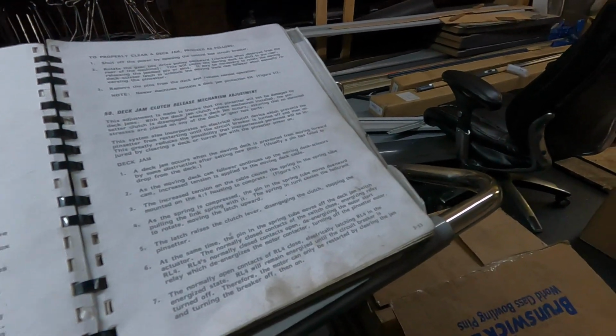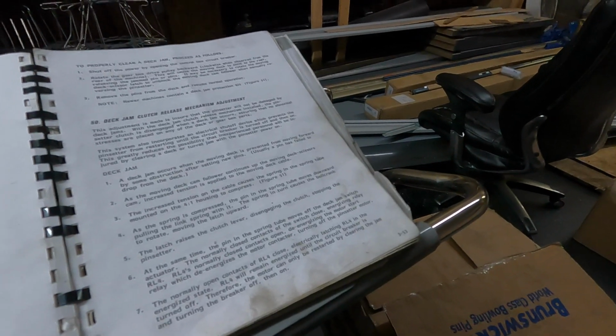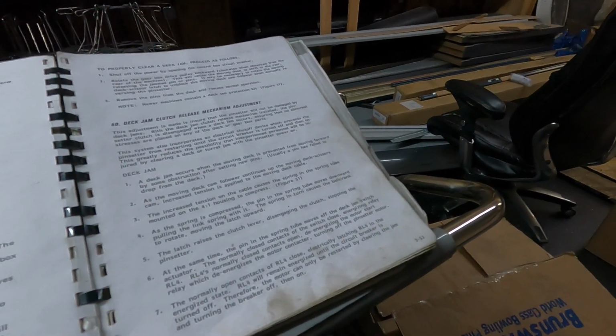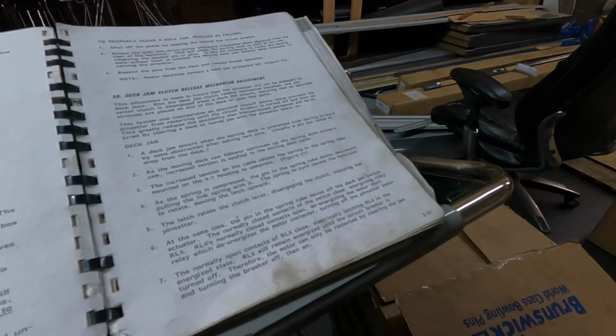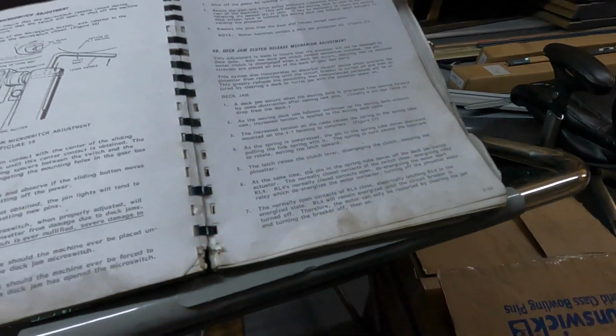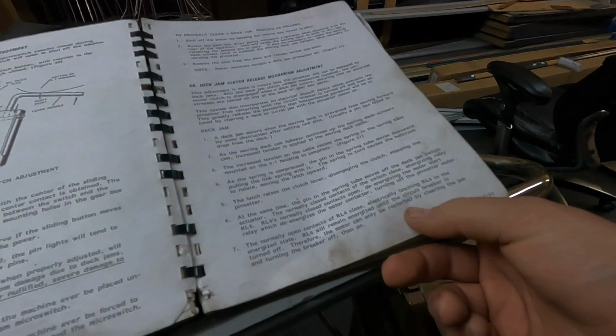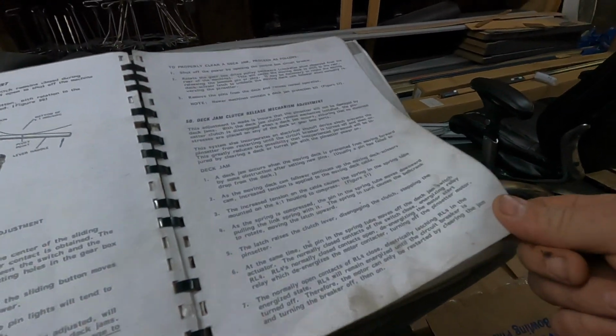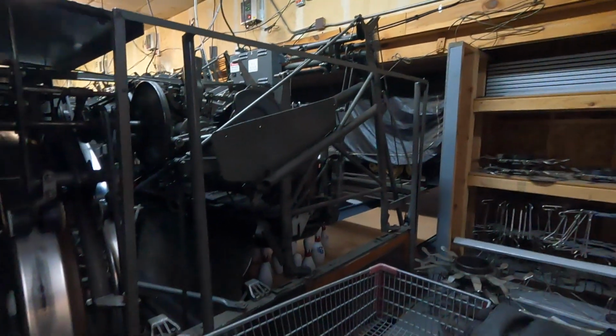Normally open contacts on RL4 close, electrically latching RL4 in the energized state. RL4 will remain energized until the circuit breaker is turned off. Therefore, the motor can only be restarted by clearing the jam and turning the circuit breaker off, then on—so the breaker on the box.